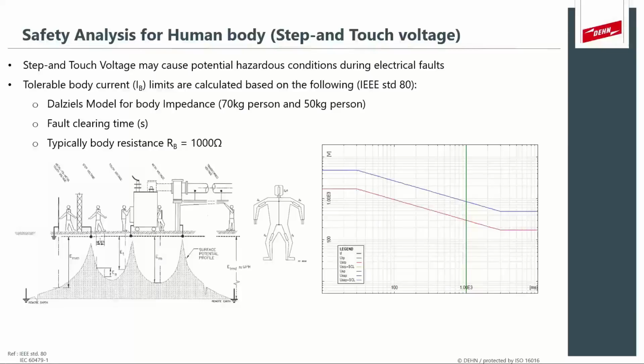So the basic concept is this: current flows when there is a voltage difference between two points. Now, if we look at this picture, which is from IEEE standard 80, if we inject a fault current at this point, it creates this voltage gradient, or ground potential rise, on the soil surface and in the subsurface layers. If a person was standing on this graph with 1 meter spacing between his feet, one foot would be on one point of the curve and the other foot would be on another point. This means that there's a voltage difference, and this voltage difference will cause current to flow through the human body, which causes electric shock. That's known as step potential.